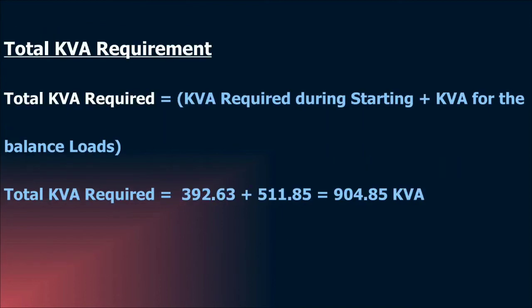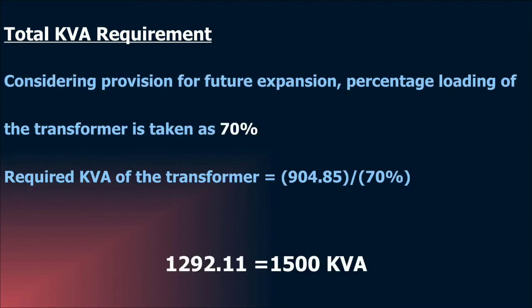Coming to the total kVA required for the system, it will be the sum of the kVA required for the highest motor plus the kVA required for the balance load, which will be coming to 904.48 kVA. While finalizing the transformer, we need to consider the provision for future expansion also. So we are applying a percentage loading of 70% on the transformer, which will be giving a value of 1292.11 kVA. The transformer capacity near to that rating will be 1500 kVA.